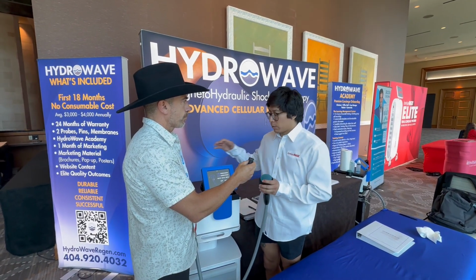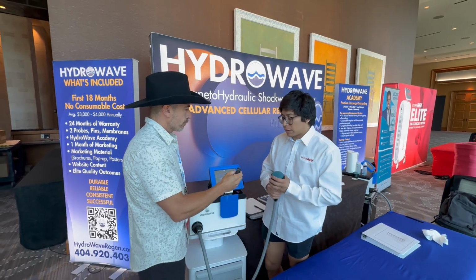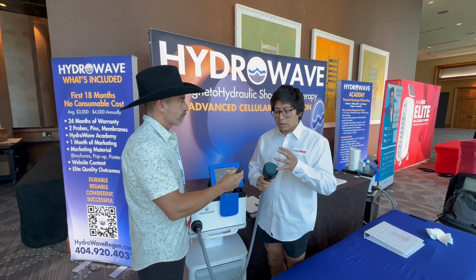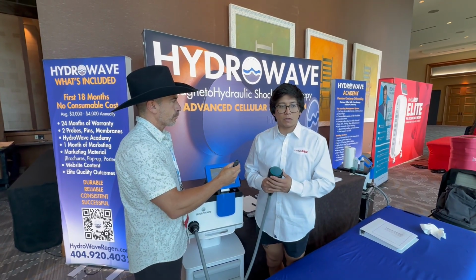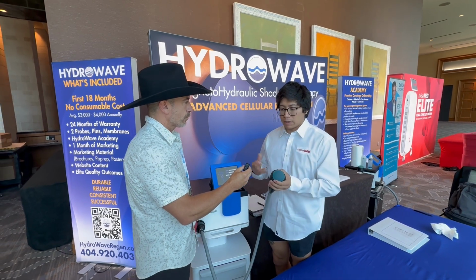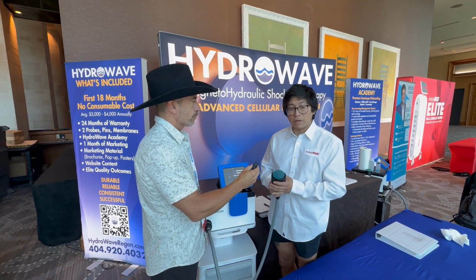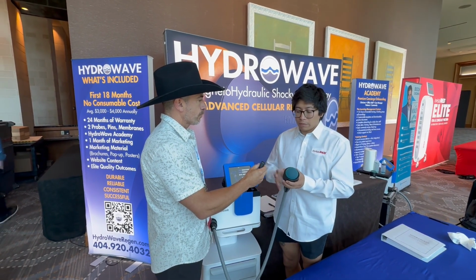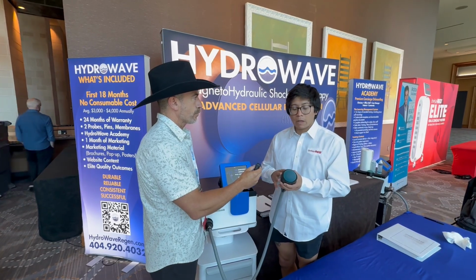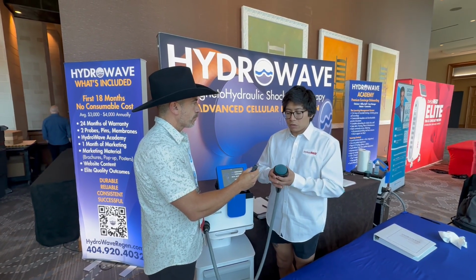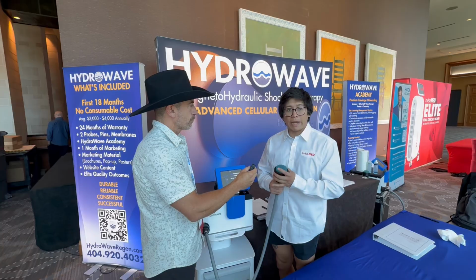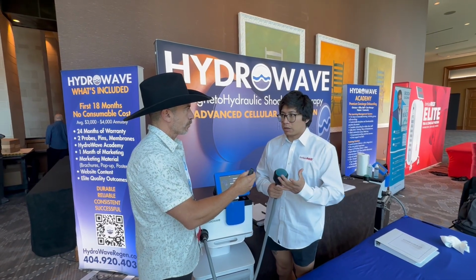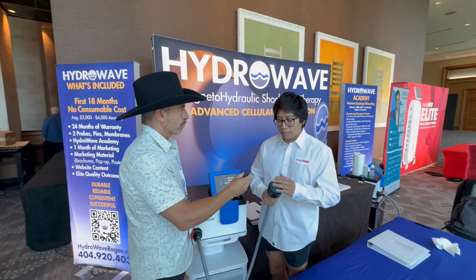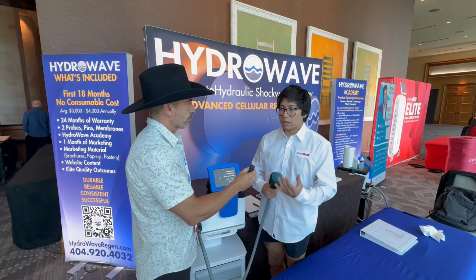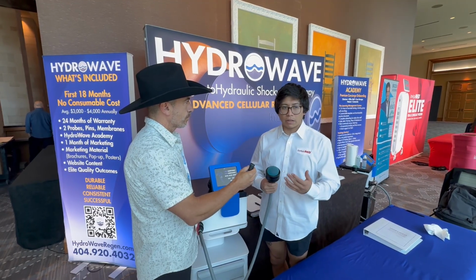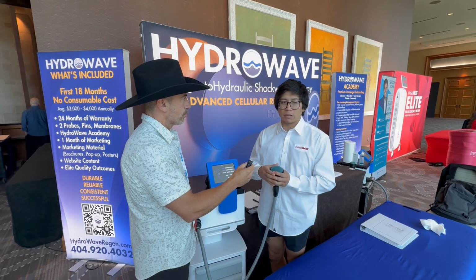So with the Hydrowave, instead of having the shock itself be exposed to water, which is one of the more corrosive things out there, we've taken it away from the water and separated them. The actual acoustic wave comes out through the electromagnet as the amplification of the acoustic wave, and the water acts as a dampener so that we can focus it or broaden the spectrum of it, so that we can treat patients on any level.